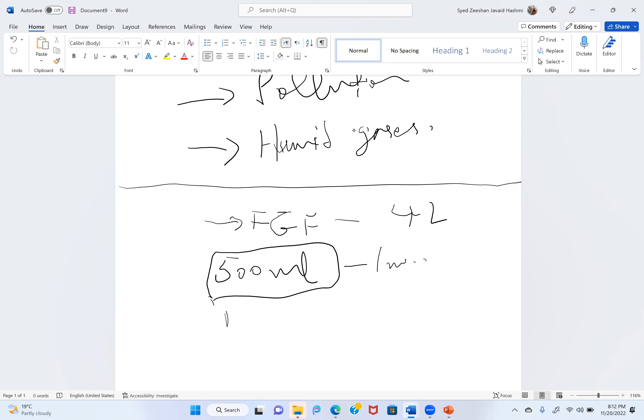So what is happening is that the expired gas which is coming is diluting the fresh gas flow. I will try to write as clean as possible. So the expired gases are diluting the fresh gas flow. For example, it has some carbon dioxide, and it has a lower concentration of oxygen. So when they mix, yes, CO2 will be removed by the soda lime. But this low FiO2 mixture will be mixing with the fresh gas flow.